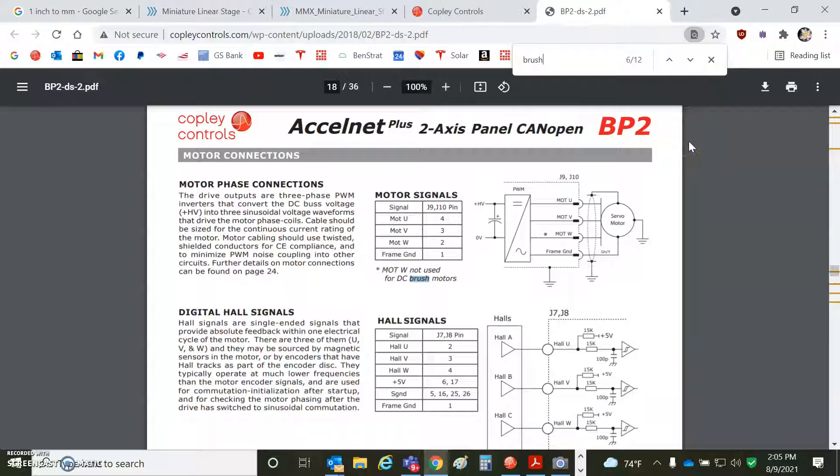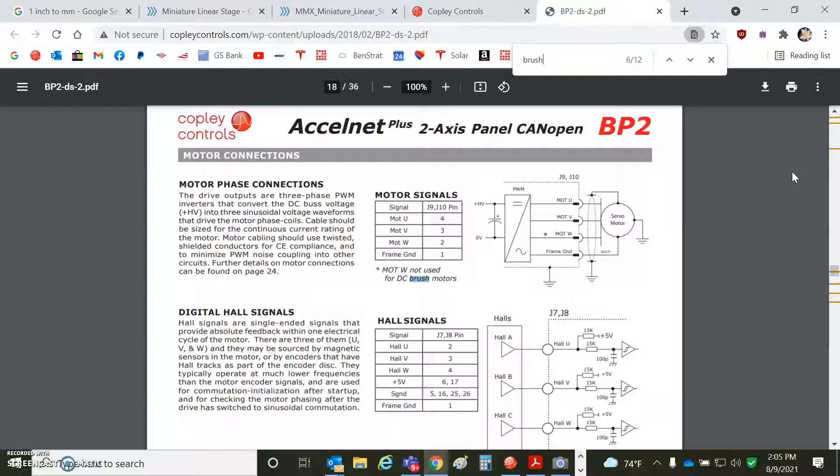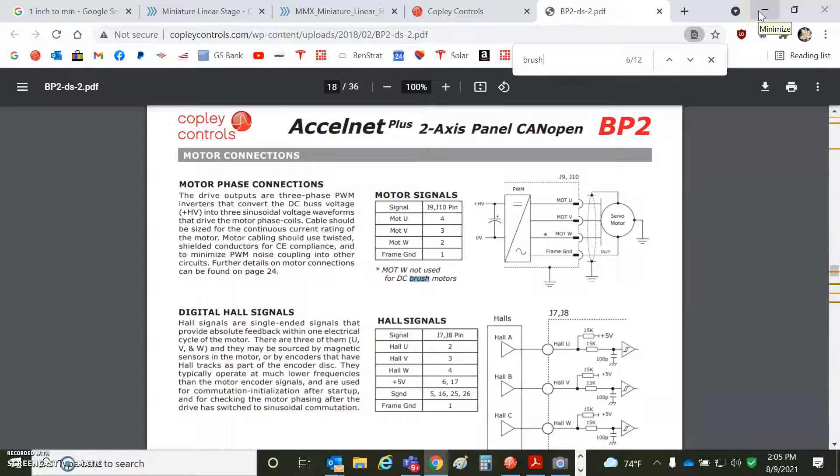And Earth at the drive. Not only the case of the drive, all cases must find a path to Earth. But the minus side of the power supply, you should connect Earth at the drive, not like a mile away at the power supply or three feet away if you're going to deliver large amounts of current. So not a large amount of current here, maybe an amp at the most. So not so bad, nice fat wire, you're good. But just Earth at the drive.